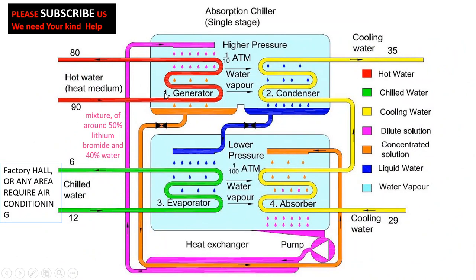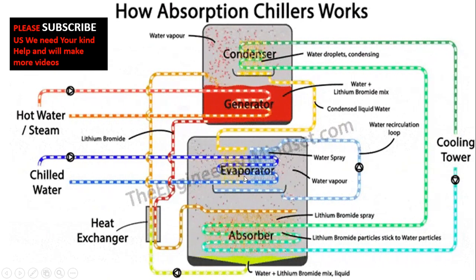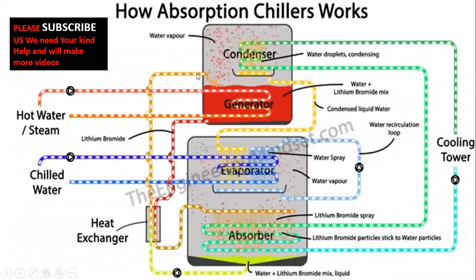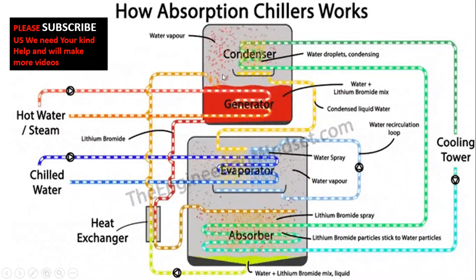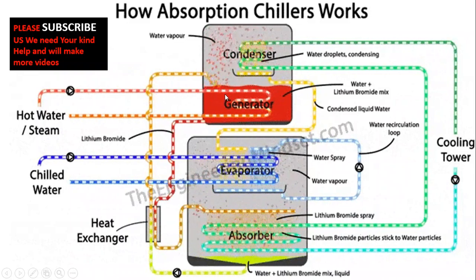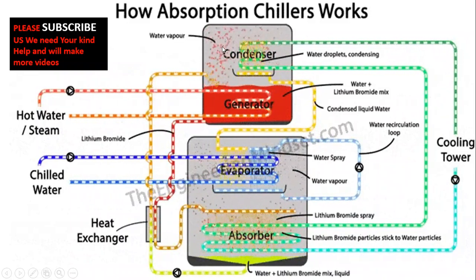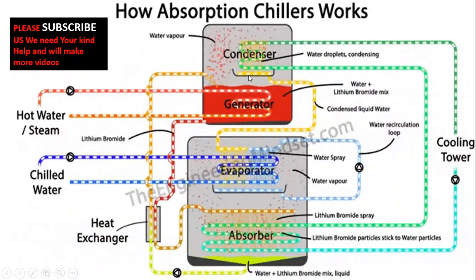All four coils are visible in the animation: the generator coil, the condenser coil, the evaporator coil, and the absorber coil. There is a cooling tower on the roof. The lithium bromide and water solution is dropped onto the hot generator coil, the water vaporizes, and the liquid lithium bromide remains. The vapors move to the condenser and become liquid pure water again.